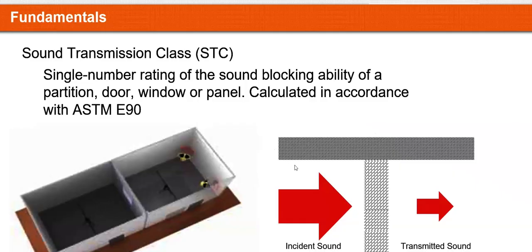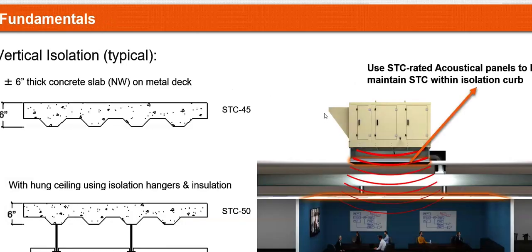The first piece of terminology as it relates to performance is sound transmission class. That's the ability of a building element to block sound. It's tested under ASTM E90. In other words, you have two reverberant chambers. One is throwing sound levels equally on all frequencies, and we measure through a hole in a partition wall to see how much transferred through without a wall or panel or louver. And then we insert the test specimen in that 4x4 opening, and we measure how much it transmitted through. We measure that difference. So that is the ability to block. Something that's very wide with a lot of density is going to do a very good job at blocking sound from transmitting through.